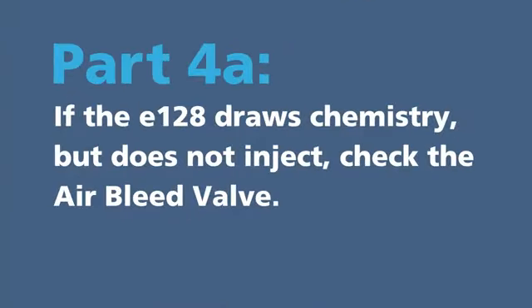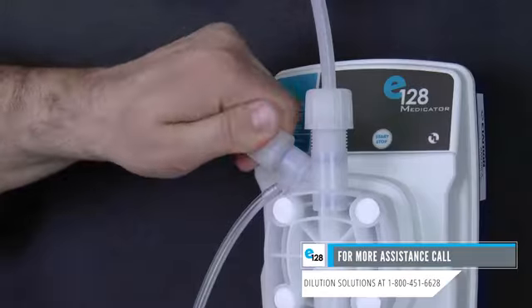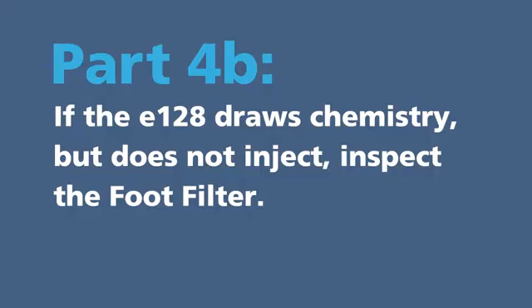Part 4A. If the E128 draws chemistry but does not inject, check the air bleed valve. It may have been left open after priming. If so, please close the air bleed valve now. Part 4B. If the E128 draws chemistry but does not inject, inspect the foot filter.